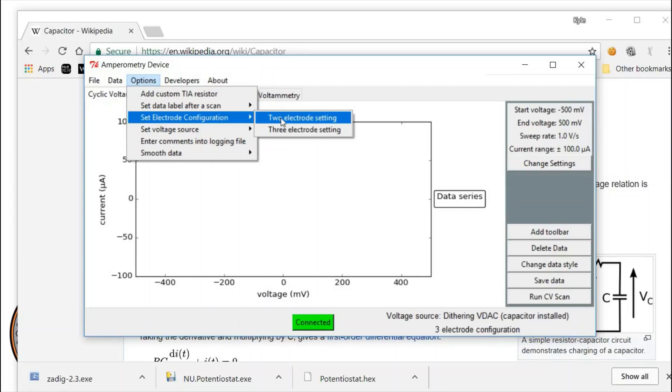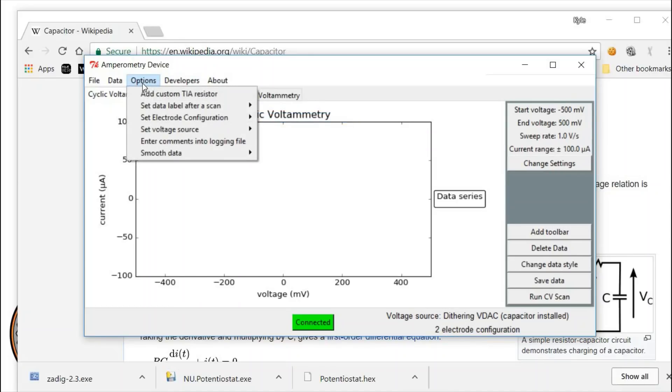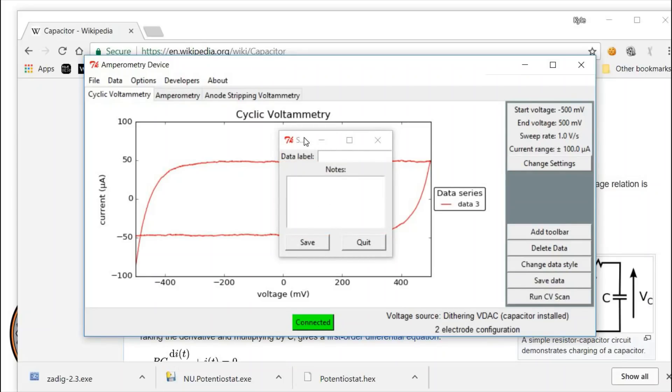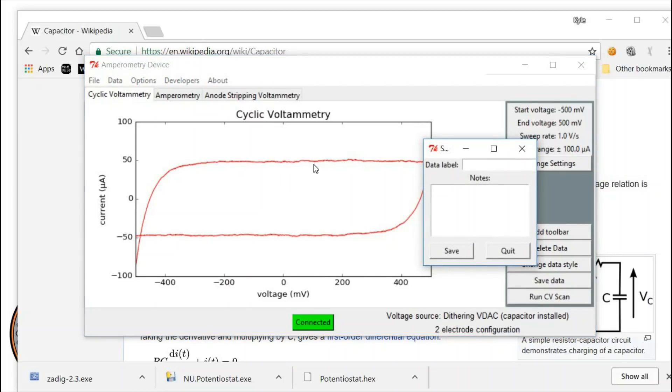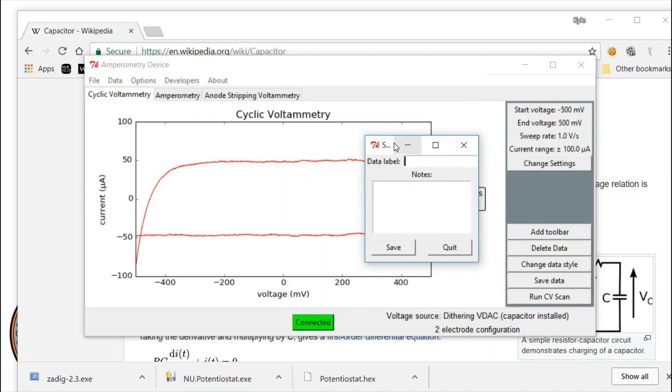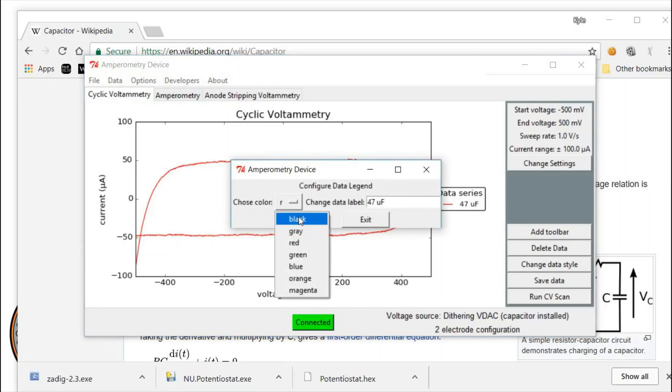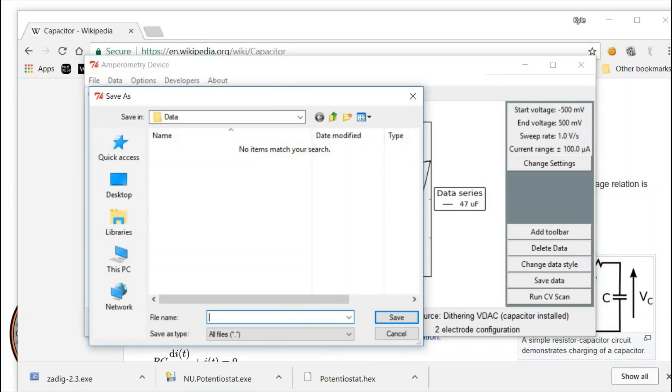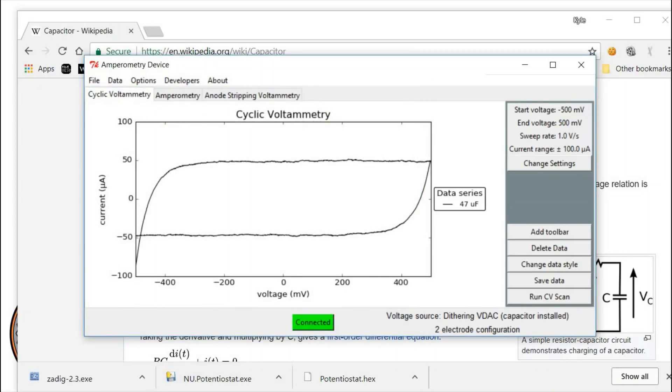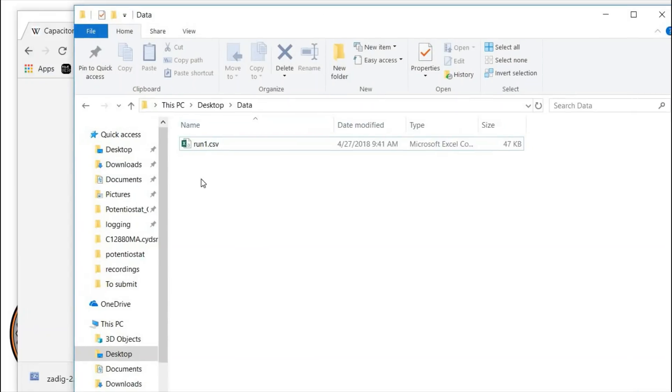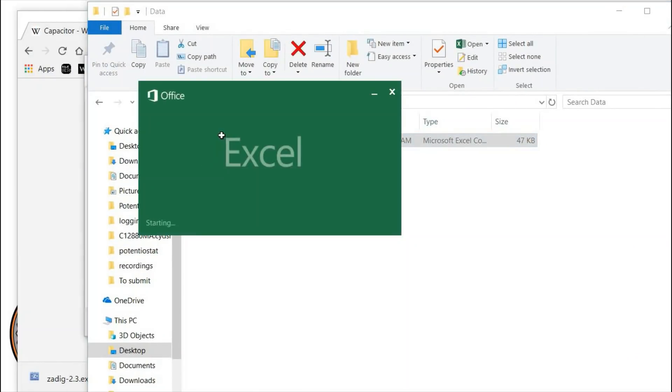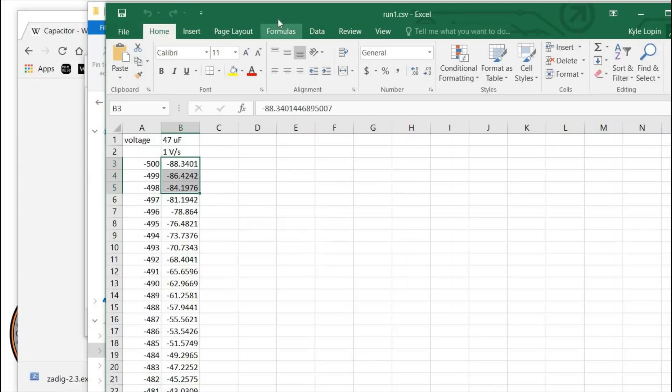To do that, we're going to change it to the 2 electrode configuration. In options, you can change between the 2 and the 3 electrodes, and it will update here so you see what it's set for. Then you click run, and the scan rate is already set. Now you see the characteristics of the sweep rates. You can put in a label, you can also put in notes here. You can change the label here if you want, or change the color, and save data. The data should be saved as comma-separated values. You go to the folder. The data is now saved with the voltage versus the current.